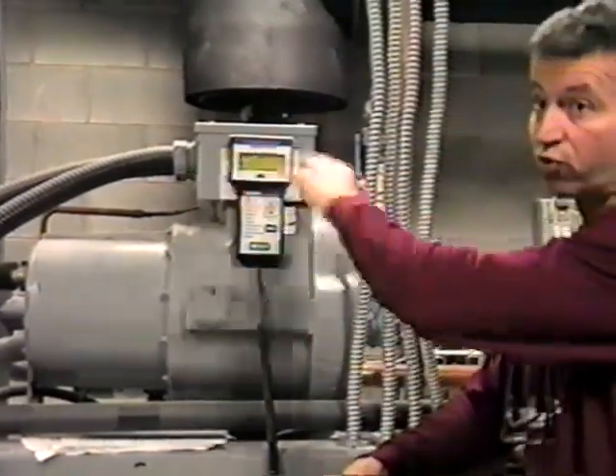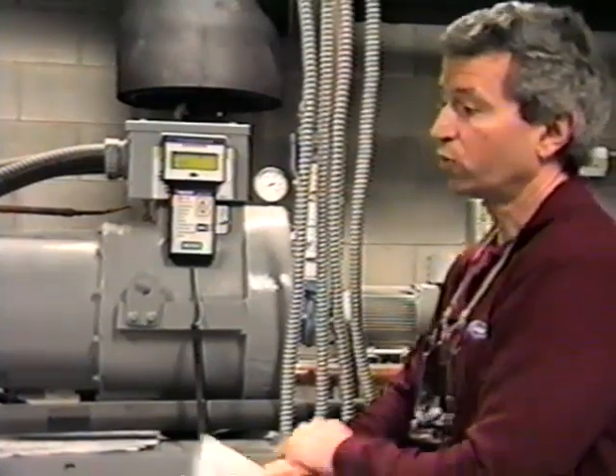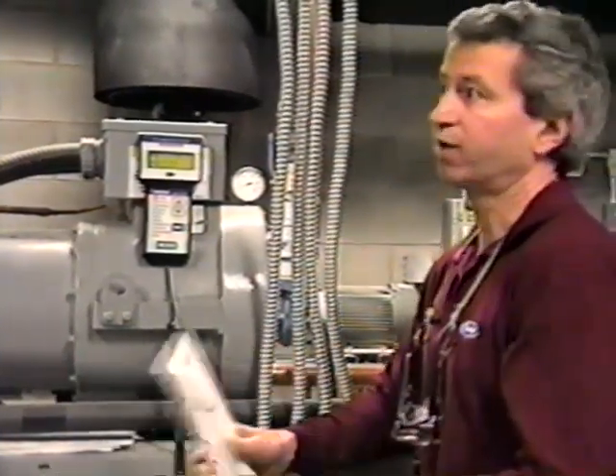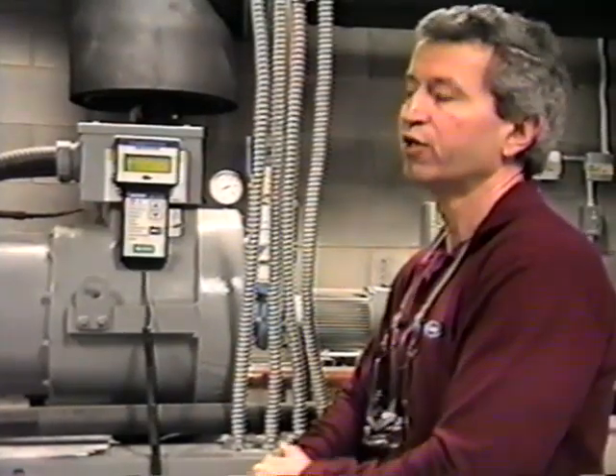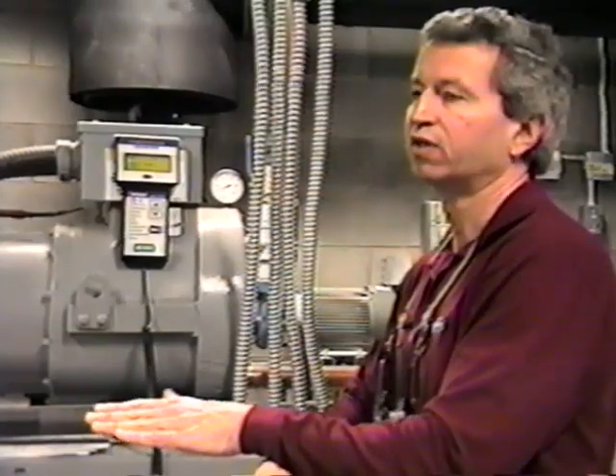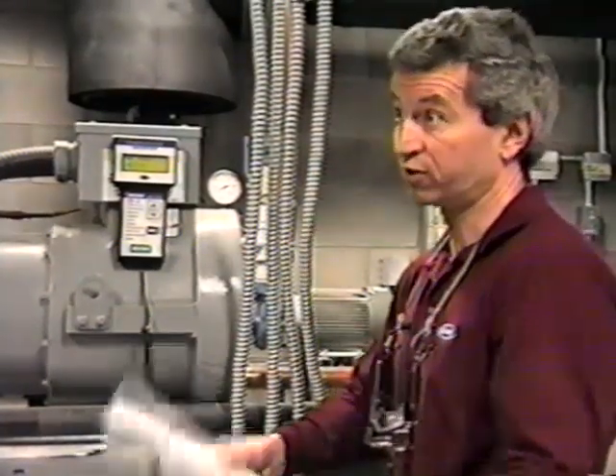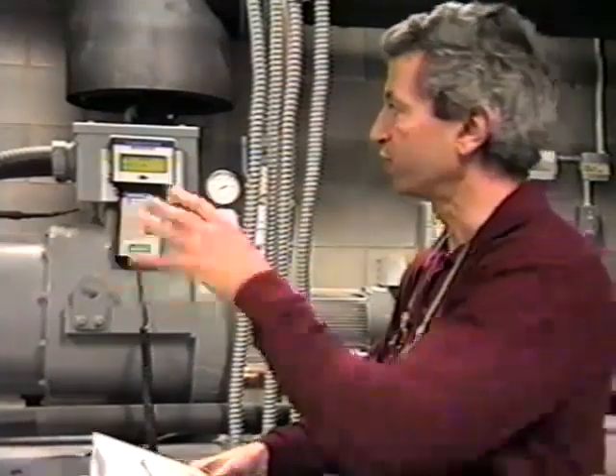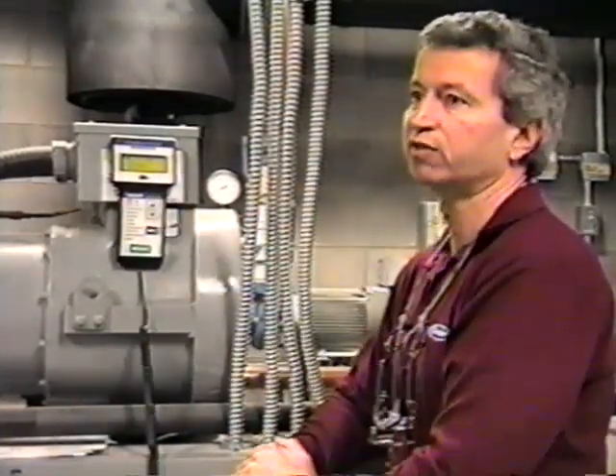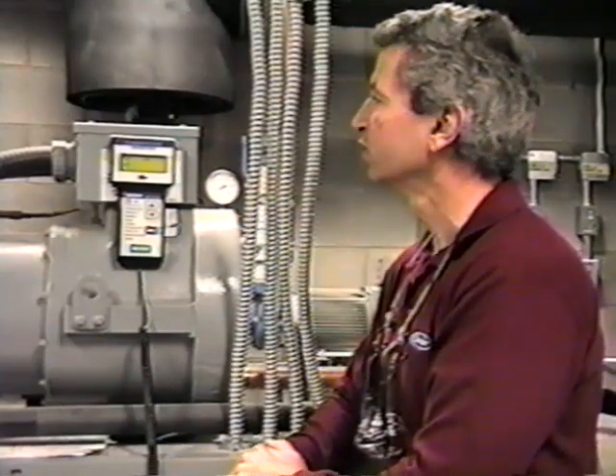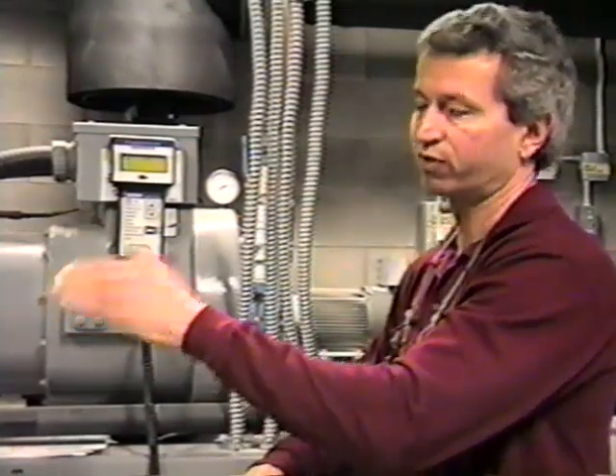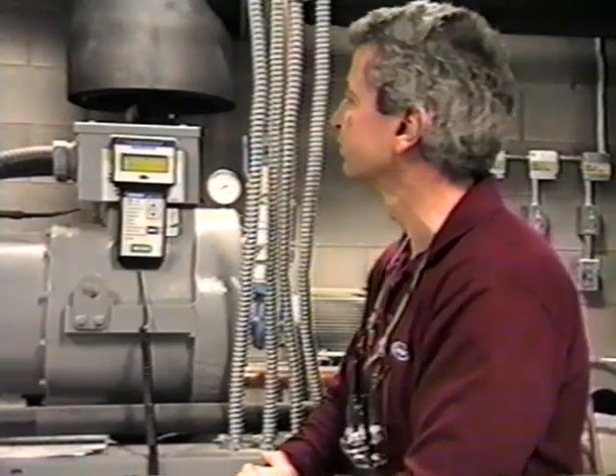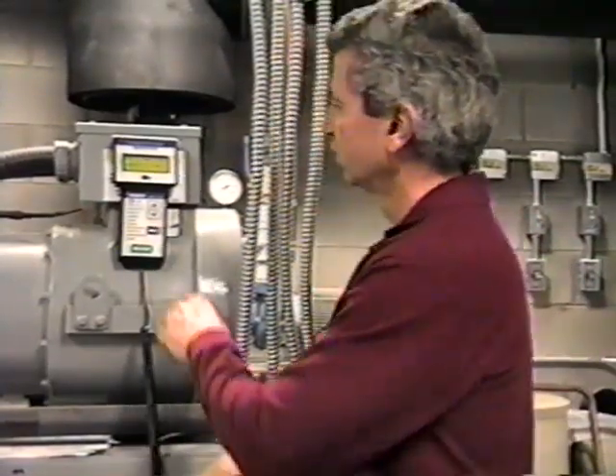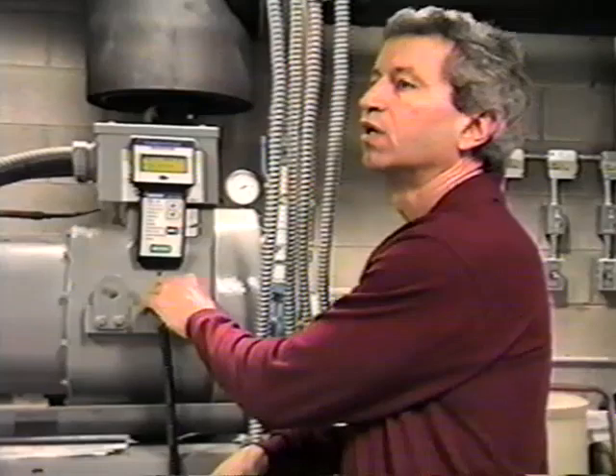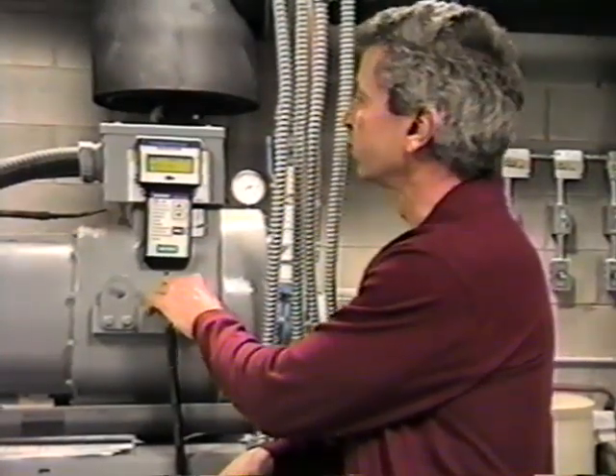You'll also notice a control point. What a control point is versus set point: if you were doing any reset temperature, I don't think you are in your panel, but you could do a remote reset of the set point, and essentially that would be considered your control point at that point, because it would be different than your set point. So that's why those two numbers will be the same on this display. Don't let that confuse you. Basically your set point is going to be your control point as far as your 15 degrees goes. When you change the ice temperature, the set point is the one that you change. Right, right. That's right.